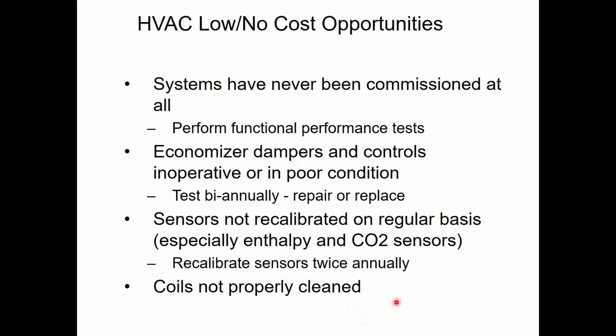You can also save compressor energy by having clean coils. Because if I have dirt on my coil, now instead of the refrigerant heating up the metal coil or cooling down the metal coil, and then that coil heating up or cooling down the air, now the refrigerant has to heat up the coil, the metal coil. Then the metal coil has to heat up or cool down the debris and dirt. Then the debris or dirt has to heat up and cool down the air. There's an extra step of process in there. Basically, the dirt acts like an insulator on the coil, and it makes it harder to cool or heat your building. So cleaning coils has an energy saving standpoint from the heating cooling standpoint and from the fan energy standpoint.